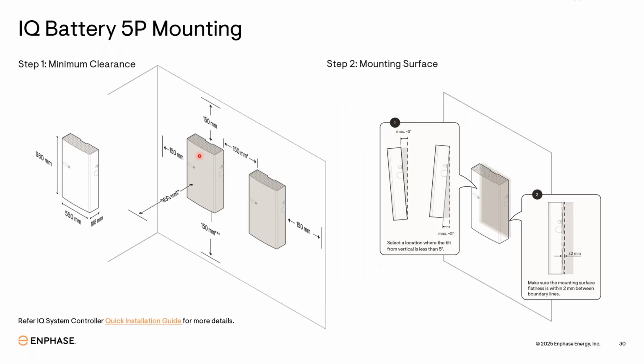For the battery, you need minimum 150 mm clearance from all four sides, and 900 mm from the front. Make sure you mount it on a solid wall, because this is 83 kg of batteries and your wall needs to bear all the load. Make sure your wall doesn't tilt more than 5 degrees, and the surface should not be uneven. So don't mount it over fancy tiles or stone tiles. Mount it over a plain wall only.